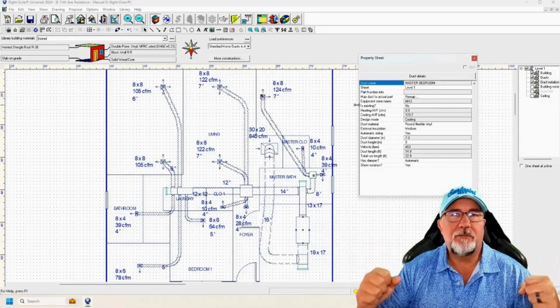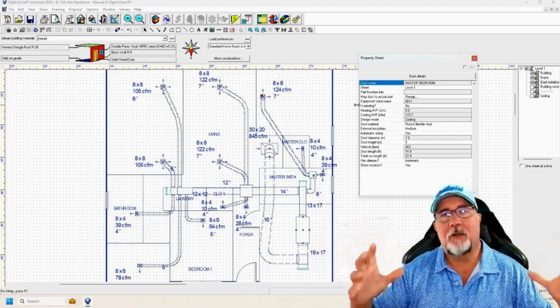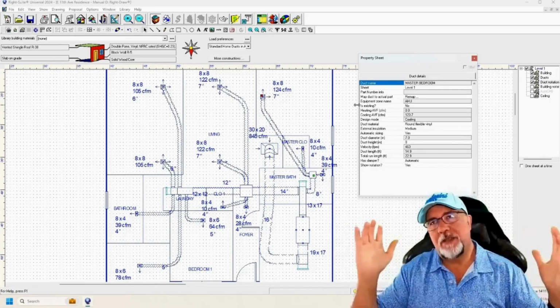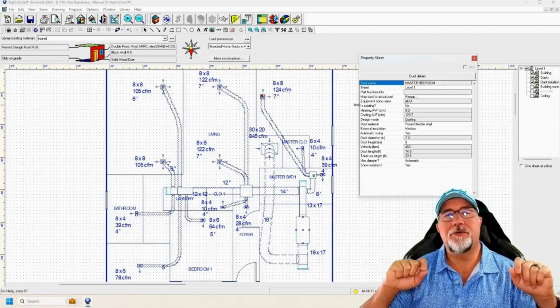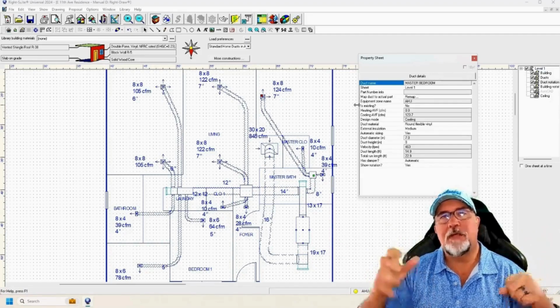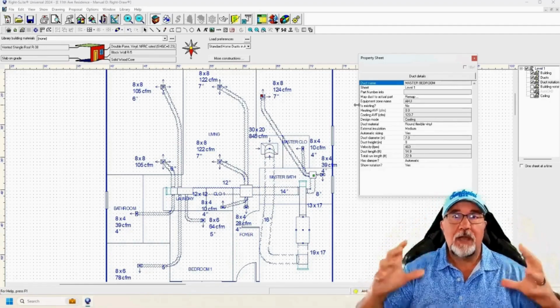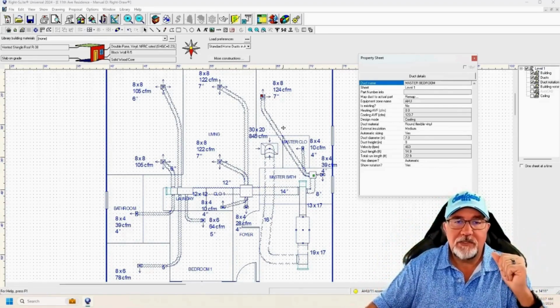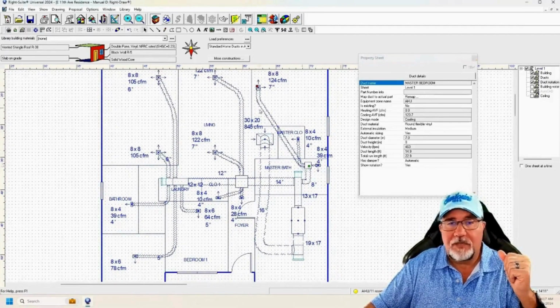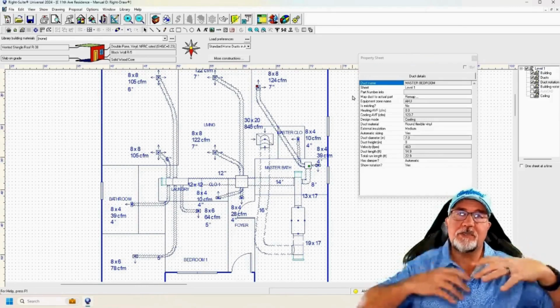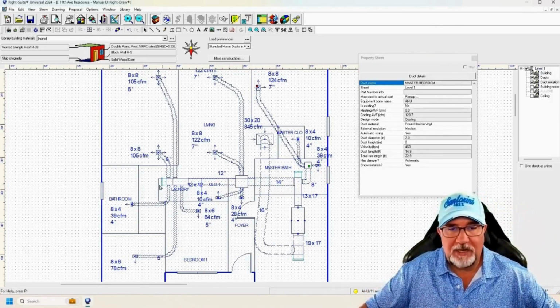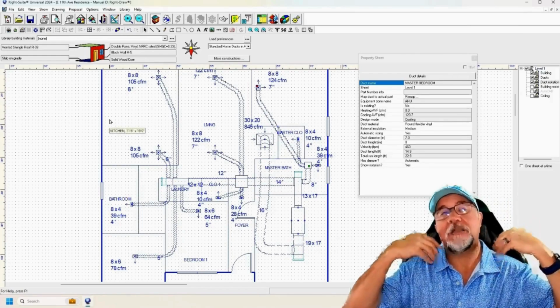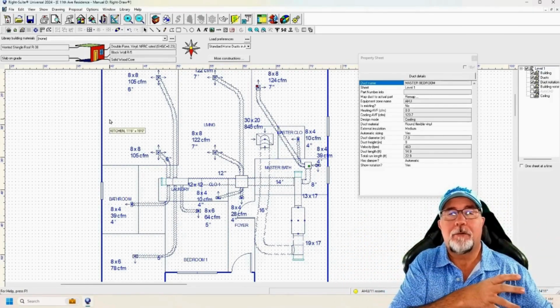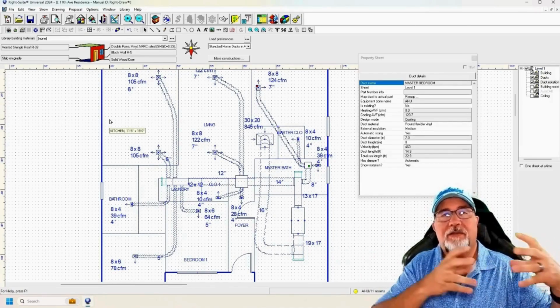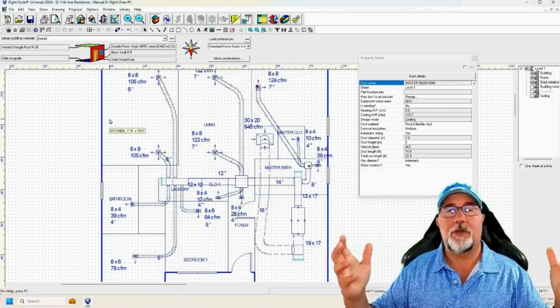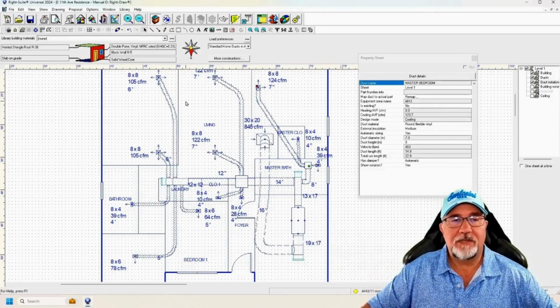So dampers are extremely important. They're actually mandatory if you're following the Manual D duct design rules. But you'll probably find that less than 10% of builders and HVAC contractors out there put dampers in their duct systems. Okay, so they have to be designed and installed. When we design this, there are all these clarifications that come into play: this duct has to be run with very minimal restrictions, and it's a certain length. Well, if somebody doesn't design this the way we have, but still uses the same duct sizes in the rooms, and they create a lot more restrictions in the duct system by the time they install it, then our design is null and void, because now there's an extra restriction in this kitchen maybe.